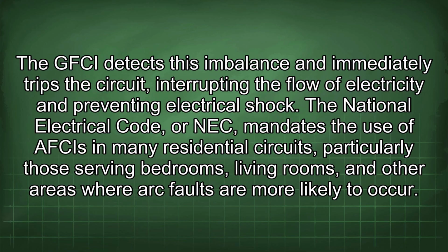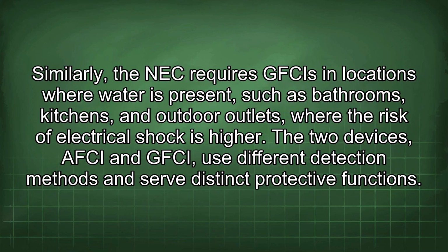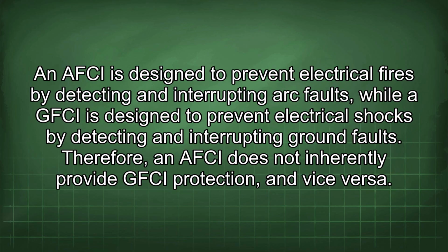The National Electrical Code, or NEC, mandates the use of AFCIs in many residential circuits, particularly those serving bedrooms, living rooms, and other areas where arc faults are more likely to occur. Similarly, the NEC requires GFCIs in locations where water is present, such as bathrooms, kitchens, and outdoor outlets, where the risk of electrical shock is higher. The two devices, AFCI and GFCI, use different detection methods and serve distinct protective functions. An AFCI is designed to prevent electrical fires by detecting and interrupting arc faults, while a GFCI is designed to prevent electrical shocks by detecting and interrupting ground faults. Therefore, an AFCI does not inherently provide GFCI protection, and vice versa.